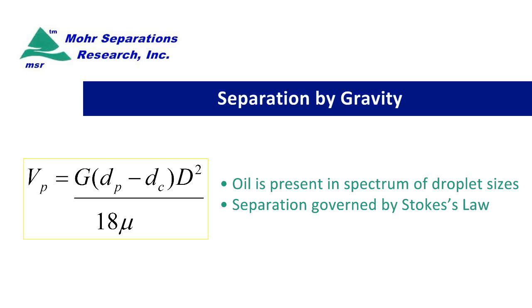The VP — that's the rise velocity of the droplets — is equal to the gravitational constant times the difference between the specific gravity, the density of the particles and the continuous phase. The continuous phase in this case is the water and the particles are the oil droplets, times the diameter of the droplets squared over 18 times the viscosity of the water.